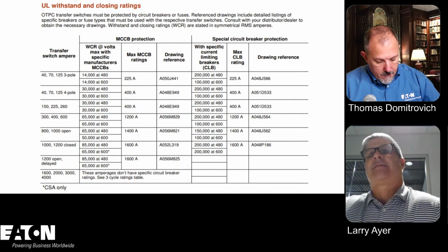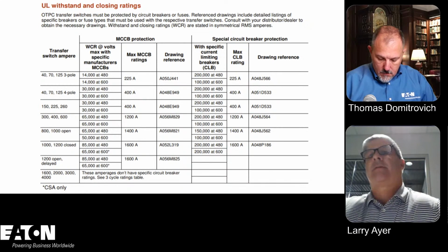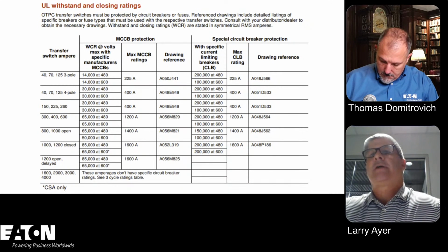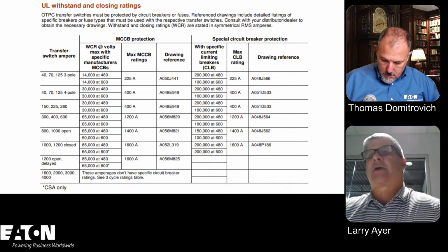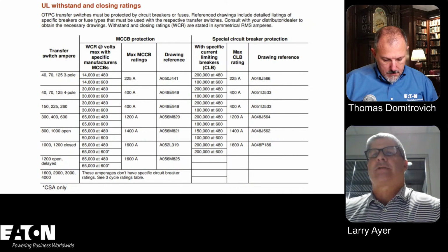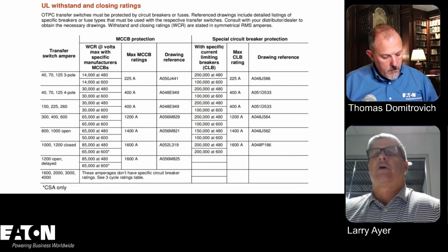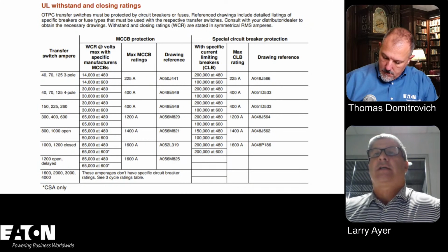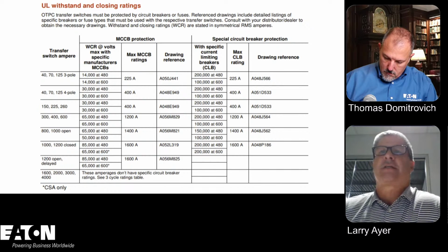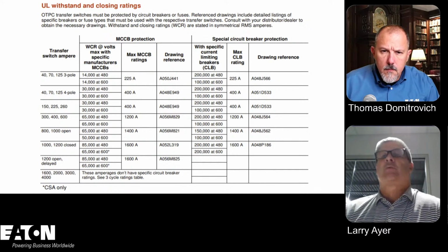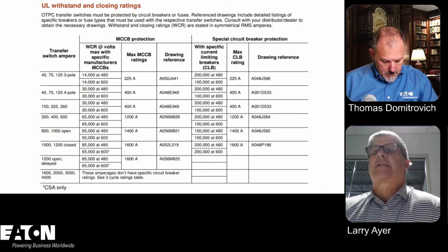If you went out and got a listed fire pump transfer switch from maybe a Cummins or another vendor, you have to size that transfer switch at 115%. For instance, if you look at some of these rows and pick out the third row, a 250 amp transfer switch, you can wire that with 250, or that's 260. I think my eyes are deceiving me, but you could wire that at 260, but you protect that with a multi-K circuit breaker at 400 amps.